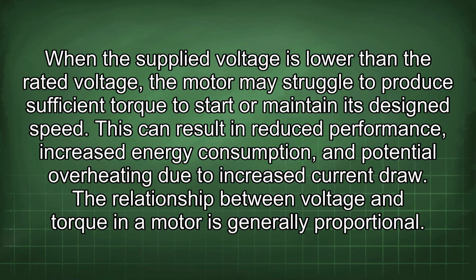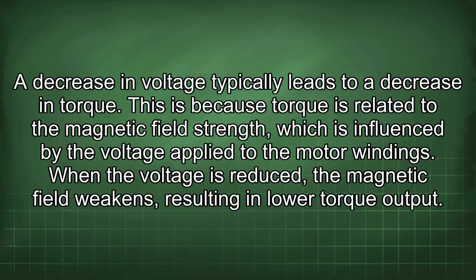When the supply voltage is lower than the rated voltage, the motor may struggle to produce sufficient torque to start or maintain its design speed. This can result in reduced performance, increased energy consumption, and potential overheating due to increased current draw. The relationship between voltage and torque in a motor is generally proportional. A decrease in voltage typically leads to a decrease in torque. This is because torque is related to the magnetic field strength, which is influenced by the voltage applied to the motor windings. When the voltage is reduced, the magnetic field weakens, resulting in low torque output.